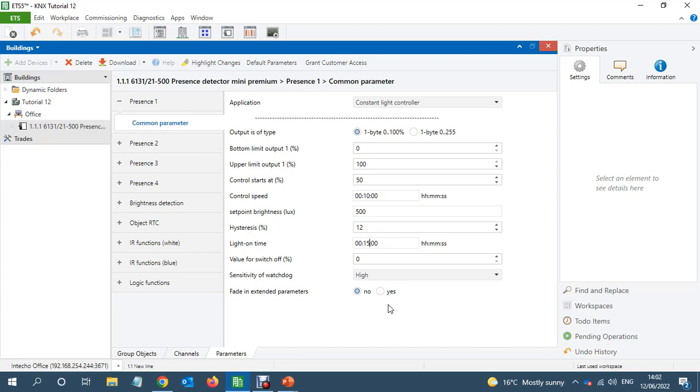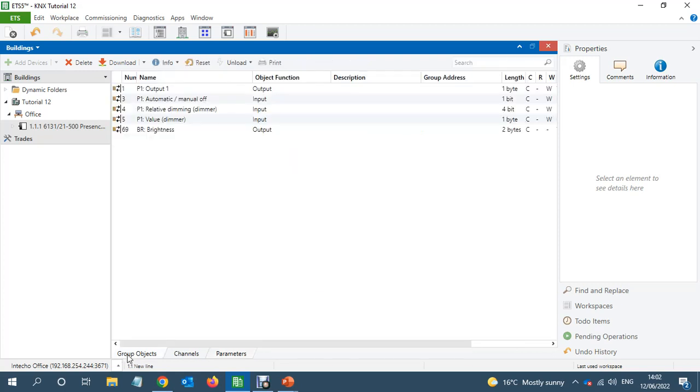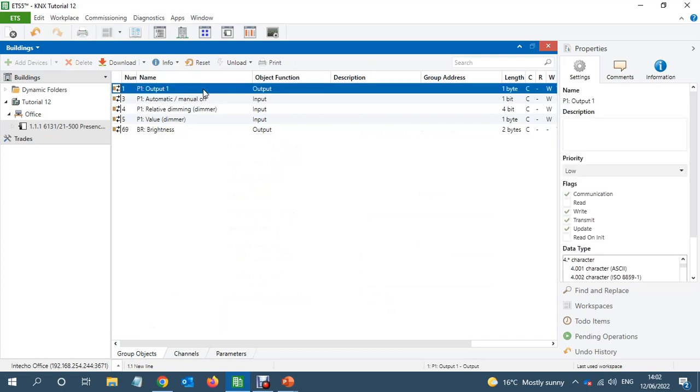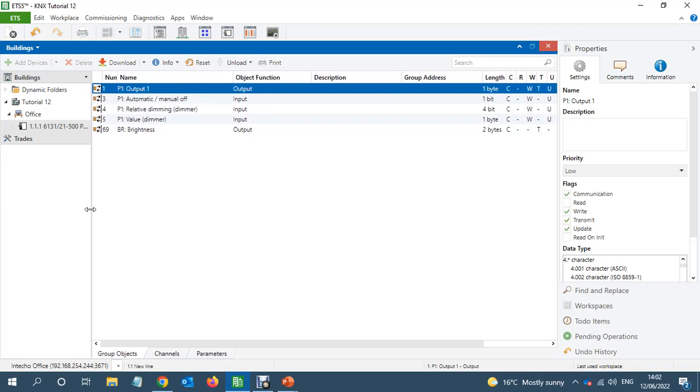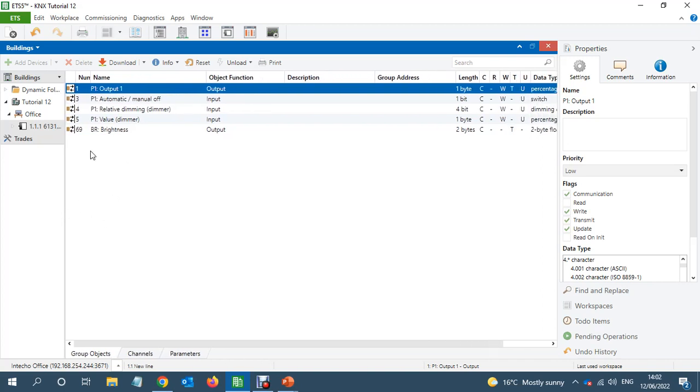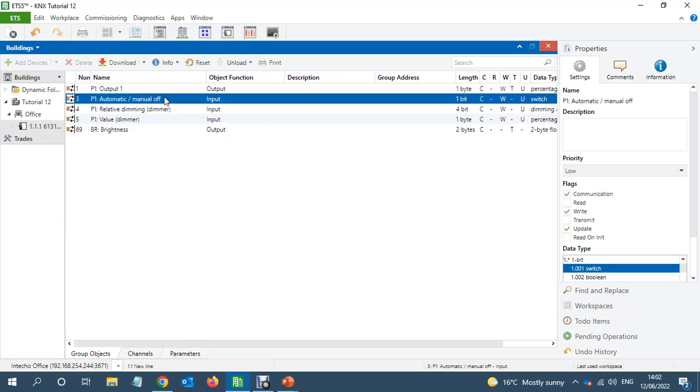And if you look at the group objects, so this is the one which we need to link with the dimming channel, one byte value. And then you see this P1: Automatic/manual off, relative dimming and value.